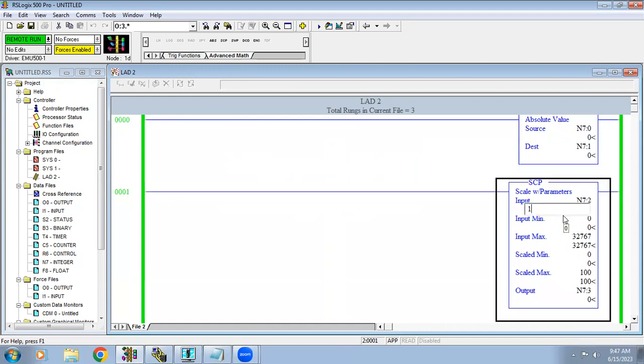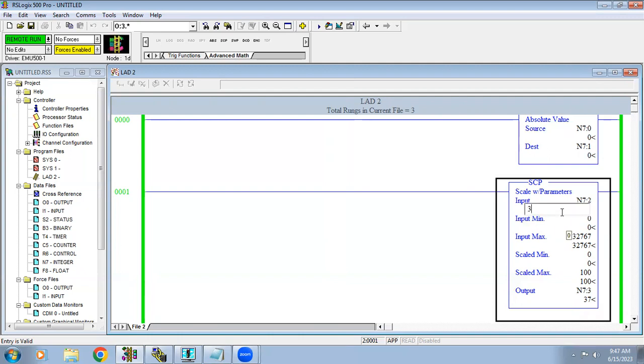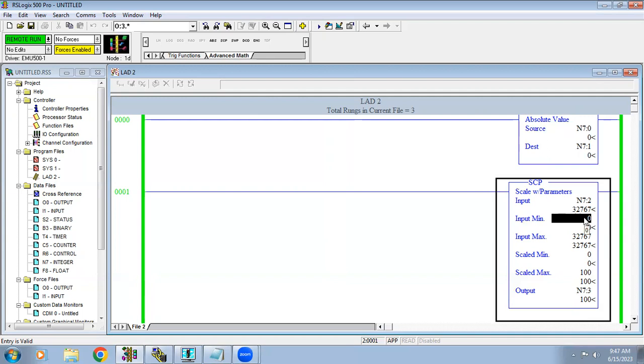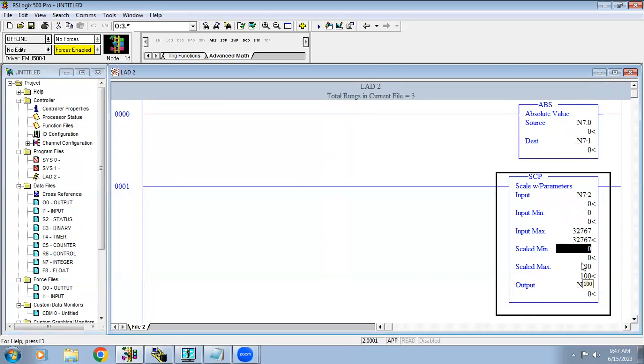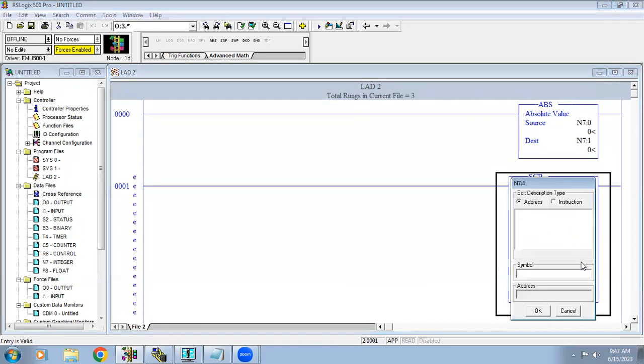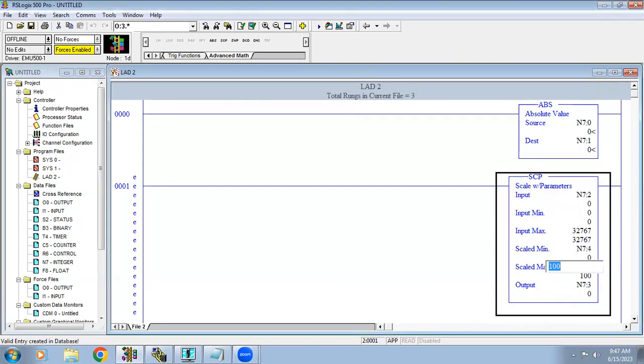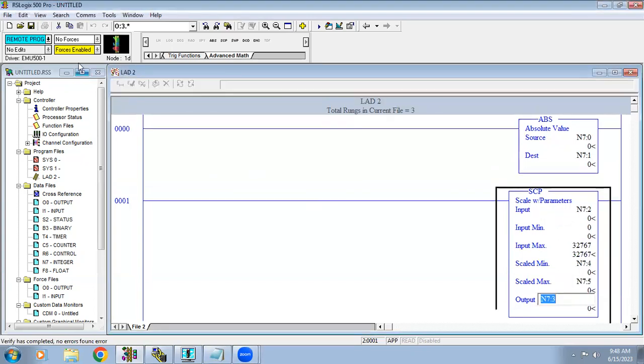Right now I'm typing 12,000 as input. Corresponding to that, in terms of percentage it displays 37 percent. If I give the maximum 32767, it will display 100 percent. Since we gave direct values in input minimum/maximum and scale minimum/maximum, we can't change them at runtime.